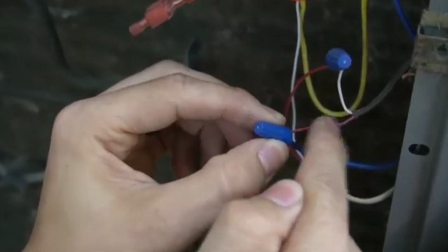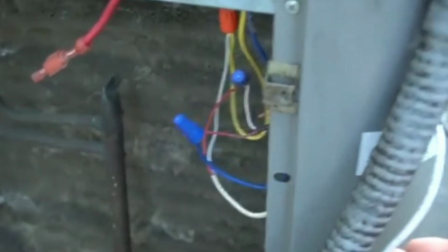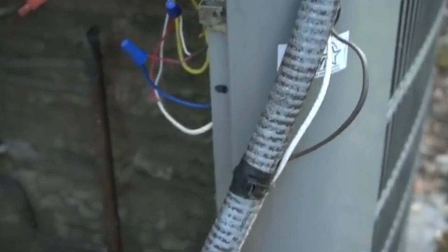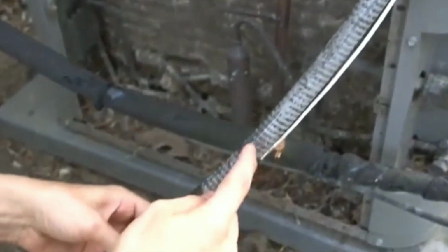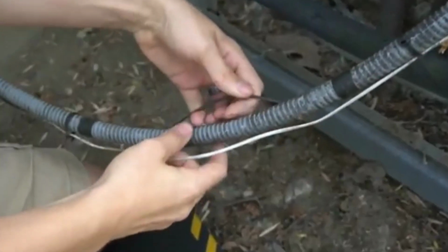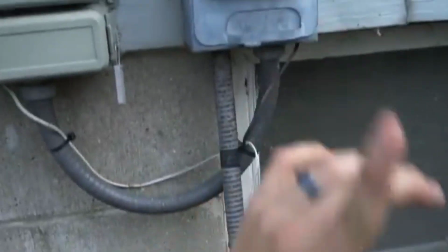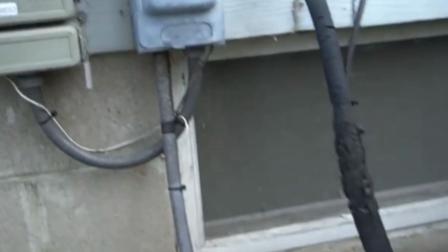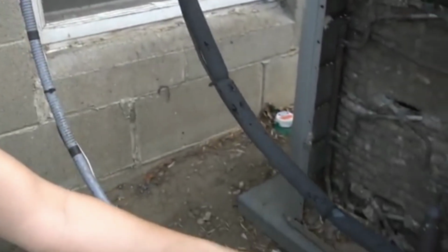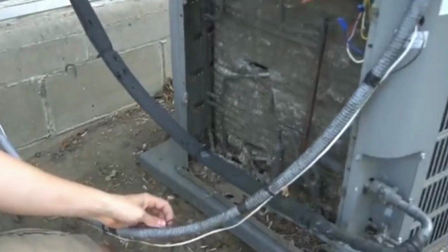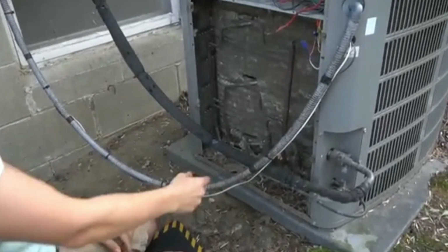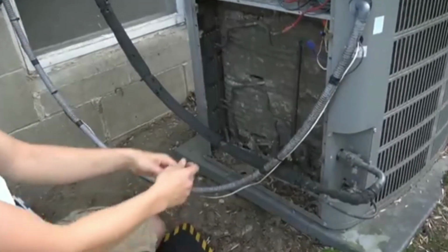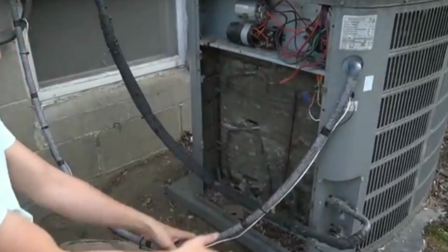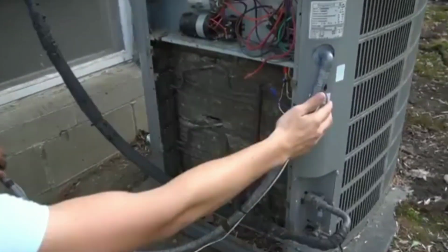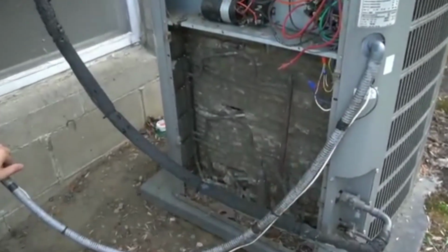And a lot of times when there's something wrong with this wire, it'll be on the outside actually. So as it runs along the whip, most of the time it'll be zip tied or somehow taped to the electrical whip right here. Just kind of runs along the side of it, goes in here, and goes into the house. Sometimes a dog will chew it. I've had customers with weed whackers accidentally chop them off. And of course, weather conditions, eventually the insulation will get a little bit brittle and start to fall apart. So as you're looking at all the wiring, make sure you take a look at that thermostat wiring going from the house to the condenser unit as well.